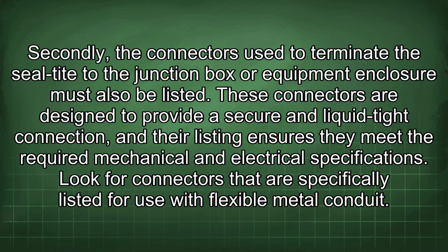Secondly, the connectors used to terminate the Seal-Tite to the junction box or equipment enclosure must also be listed. These connectors are designed to provide a secure and liquid-tight connection, and their listing ensures they meet the required mechanical and electrical specifications. Look for connectors that are specifically listed for use with flexible metal conduit.